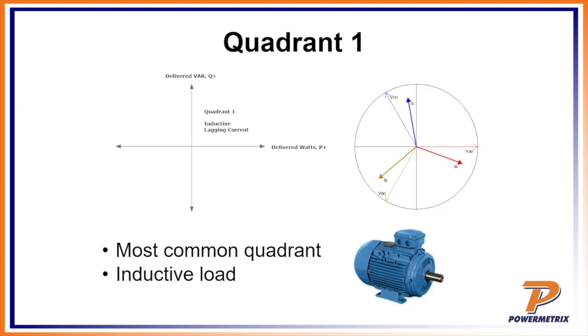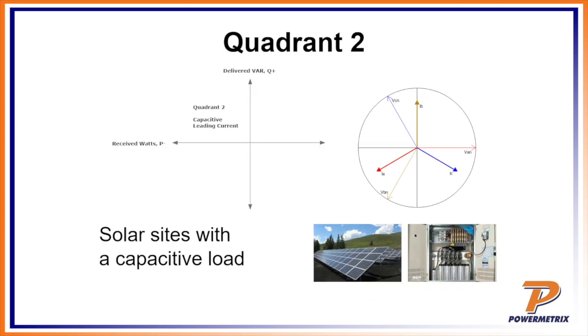Quadrant one is a very common lagging power factor you'll see in the field—think of this like a non-solar site. It's pretty obvious when you see a commercial or industrial site with a shifting power factor, about a 15-20 degree phase shift lagging. That's what we call quadrant one. Notice that in the documentation, quadrant one is at the top right, but the power master vector is on the bottom right. That's a commonly inductive load.